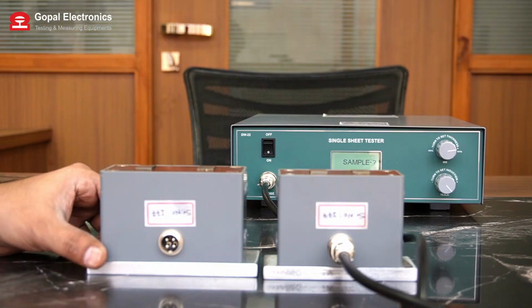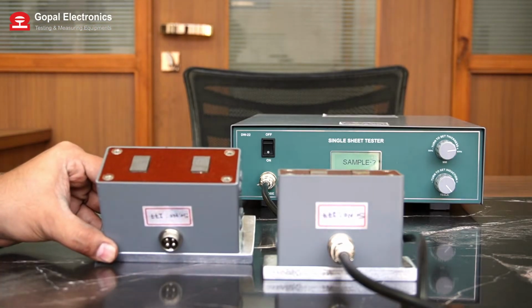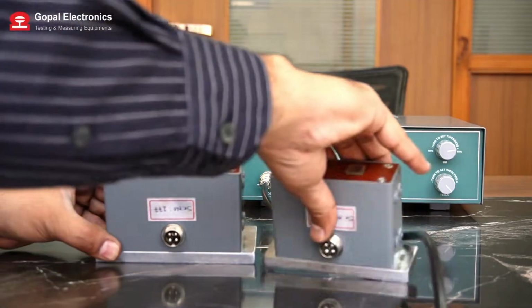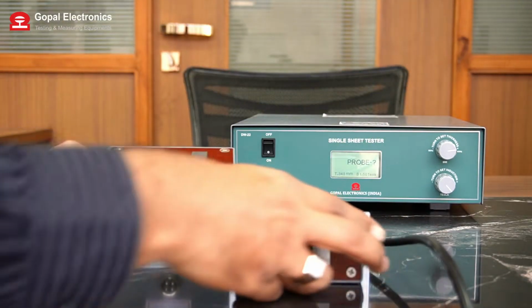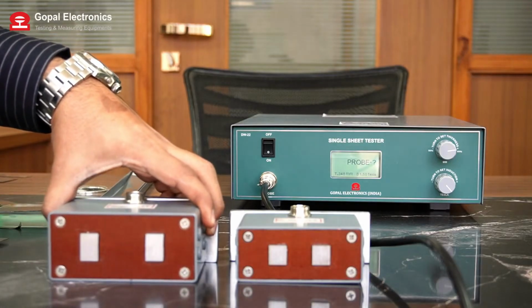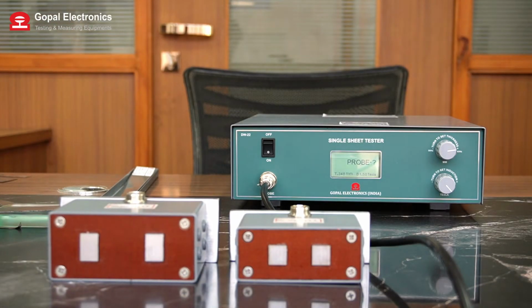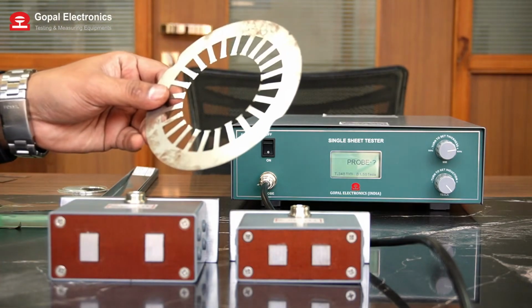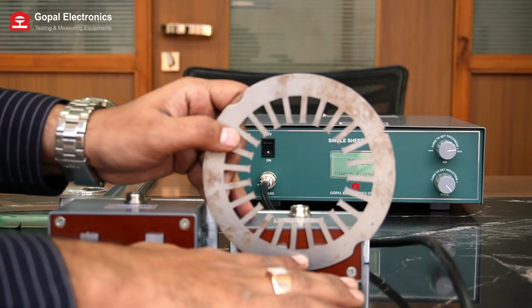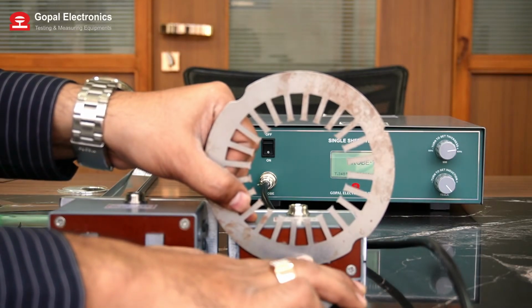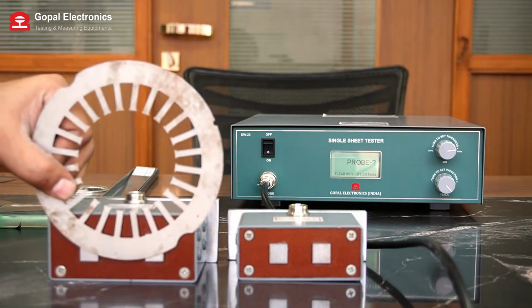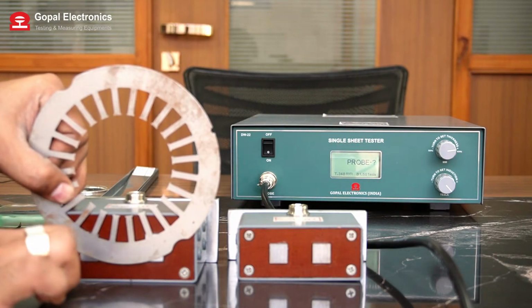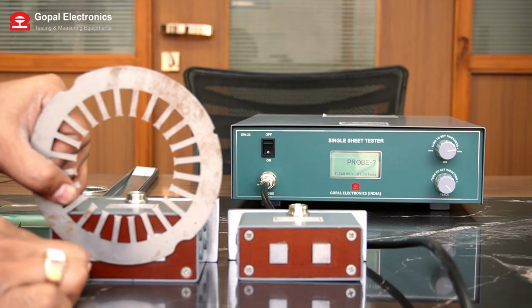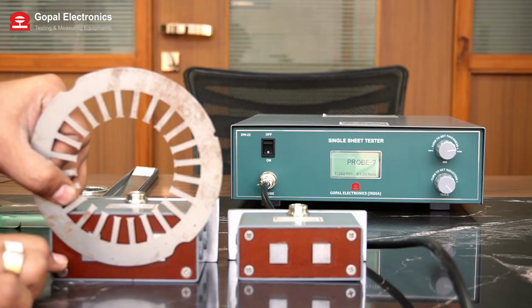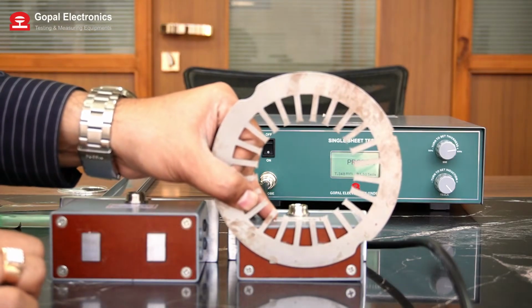In this equipment we have two types of probe. One is a bigger probe, one is a smaller probe. You can check the core area over here. So when you have smaller samples like this motor stamping, you can select a small probe. You can check the core area is covered in the smaller probe, but not possible with the bigger probe. In the bigger probe, a bigger portion of the core is not covered, so this could give a false reading, but in a small probe you can get a perfect reading in a motor stamping.